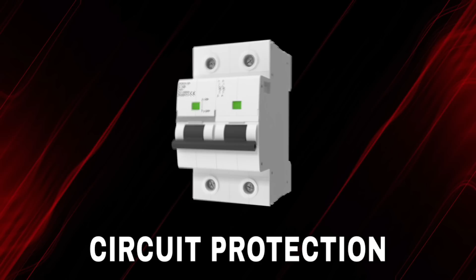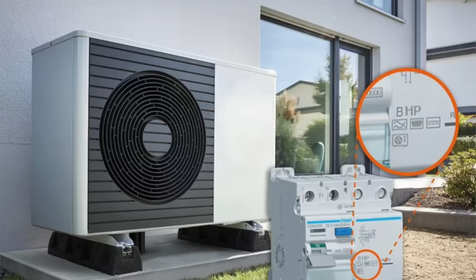Circuit protection, that is. Hager says its Type B HP RCDs are specially designed to handle the high-frequency residual currents found in heat pumps. Its device provides protection against currents over 20 kHz, ensuring a minimum tripping threshold of 150 mA for frequencies above 1 kHz. This is far beyond the capabilities of standard Type B devices. It can also tolerate DC currents without becoming magnetised and compromising its functionality. The company emphasises that Type B Plus devices are not recognised under BS 7671.